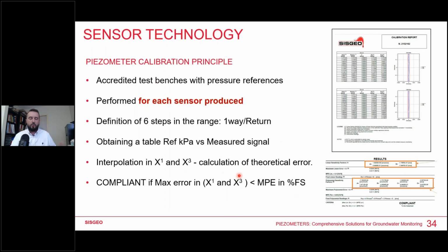Then, when you get the signal, you have to convert it into engineering units, for example, Pascal or meter of water. For that, you need a calibration. So Sisgeo is proud to provide a very dense and complete calibration report for almost all the sensors that we are producing in the full catalog, especially for piezometers. Each sensor that you receive goes through this calibration process.